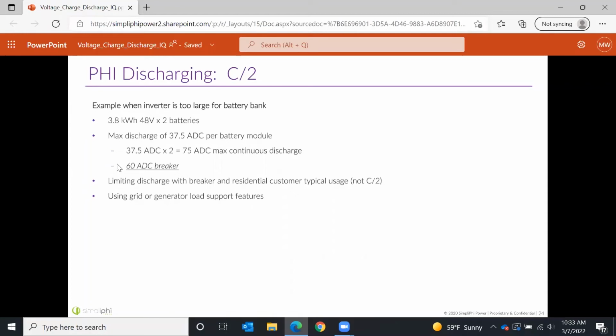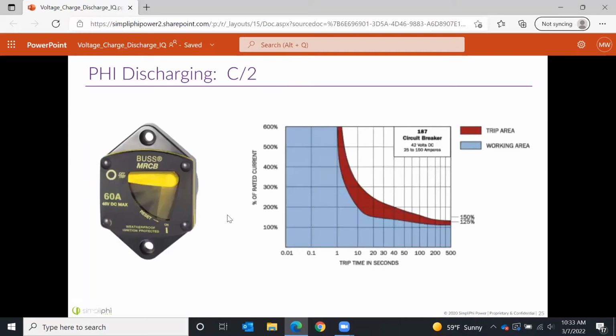You pick a 60 amp breaker, and why do you do this? Why is this an issue, right? So this breaker at 60 amps, it's going to trip when you're at approximately 120% of its rated capacity. So 120% of 60 amps is 72 amps. So that's just about perfect. And it's going to take almost 500 seconds to trip. So that's about 10 minutes right there.